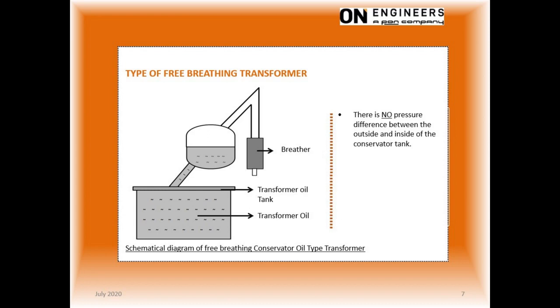A silica gel breather will be used to remove moisture from the outside air. This will prevent the contamination of the oil with moisture from the outside air.